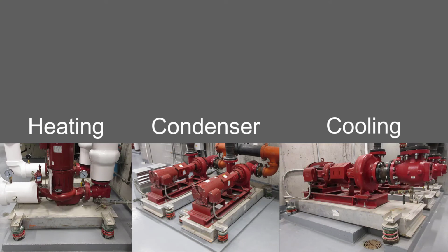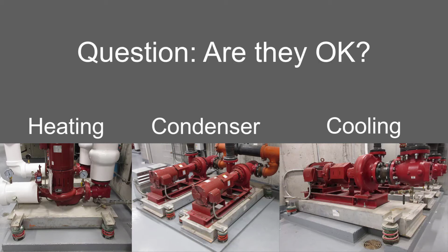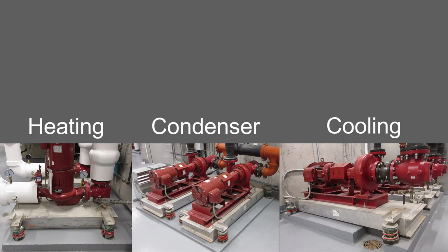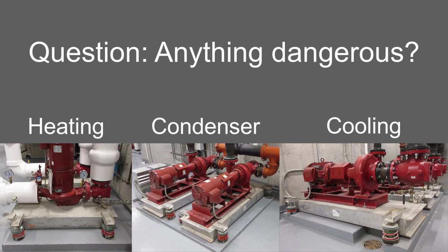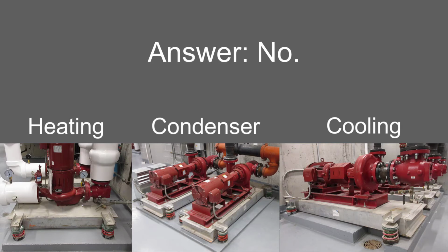We're going to review these inertia-based installations and see how they compare to the datasheets and installation instructions. We're going to determine if these installations are close enough or if we need to tell the contractor to do something further. But first, let's answer a more important question. Did we see anything dangerous? The quick answer is no. Nothing we saw creates a condition that could lead to imminent failure of equipment support or function. We also didn't see any damage to any of the bases or isolators.